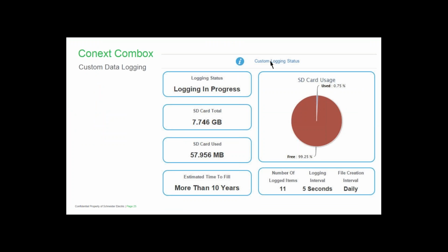Custom data logging allows specific parameters to be monitored over time. This requires a micro SD card to be inserted into the ComBox. This can be extremely helpful when troubleshooting from a remote location, saving time and money and possibly eliminating return trips to the site.